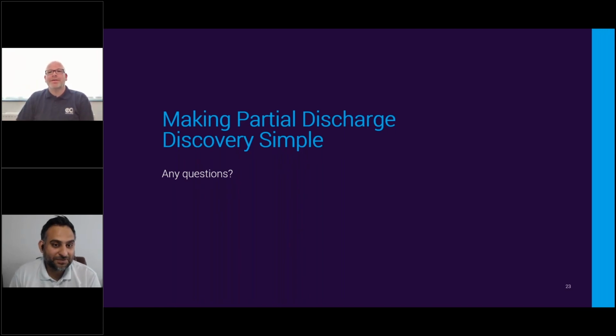So one way is obviously looking at what level of activity you're picking up, and how critical the asset is to the asset owner. So if you can live with some PD activity while you plan in some maintenance activity, then you can install some monitoring system and monitor it. But typically for anything 30 dB or above, we normally say you need to plan in any remedial actions as soon as possible. And if you can't do any remedial actions, at least investigate the source of the activity, whether that's internal PD or surface PD, so that you can plan in what remedial actions you need to take.